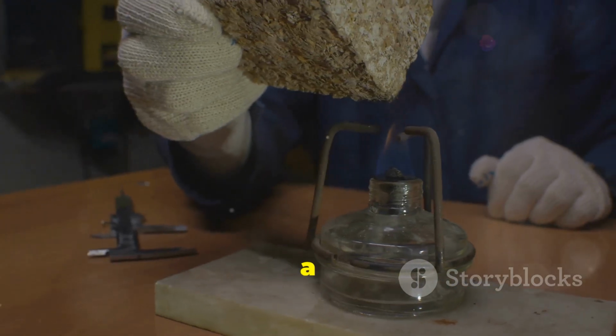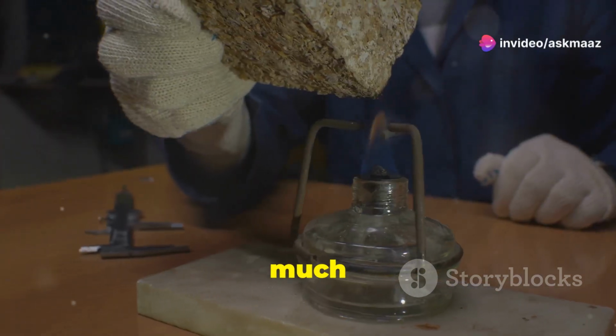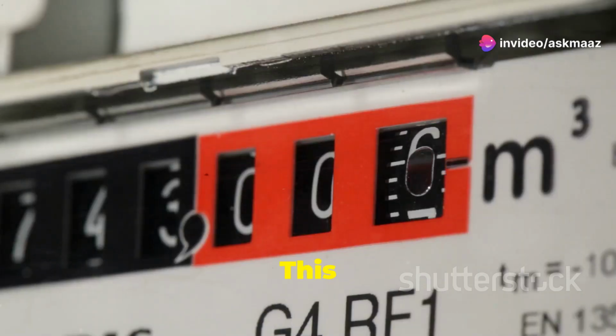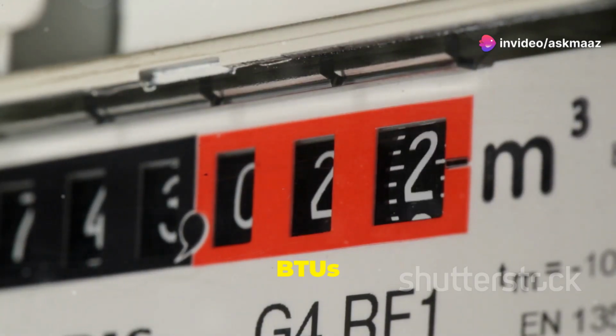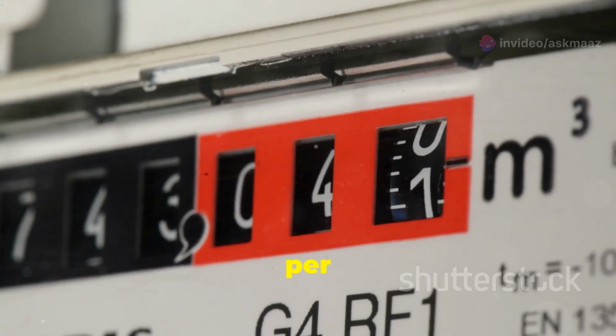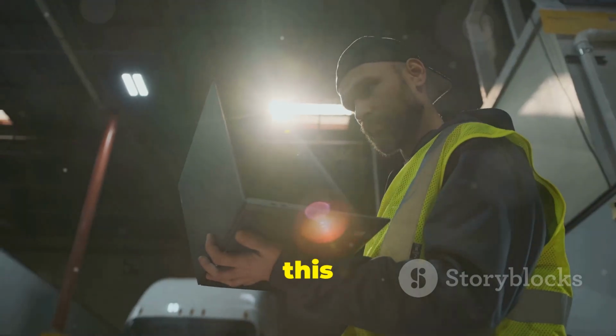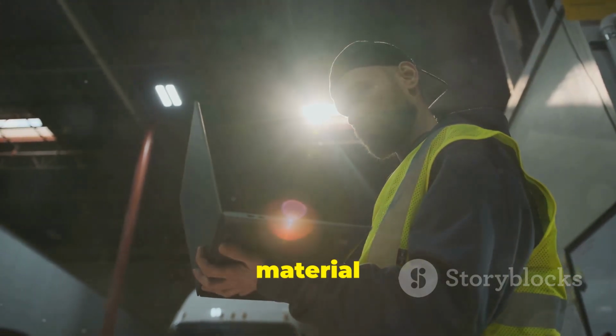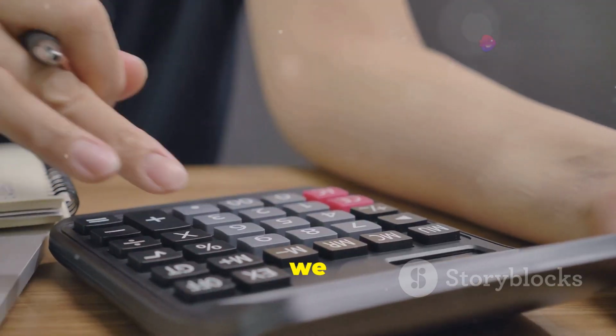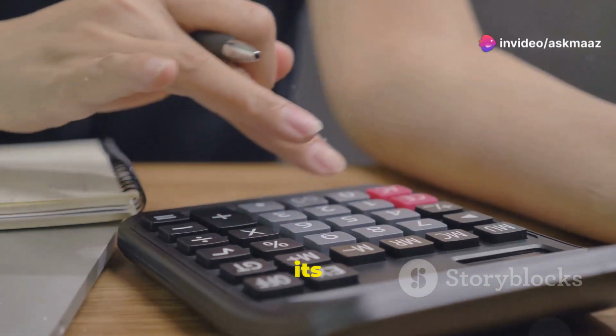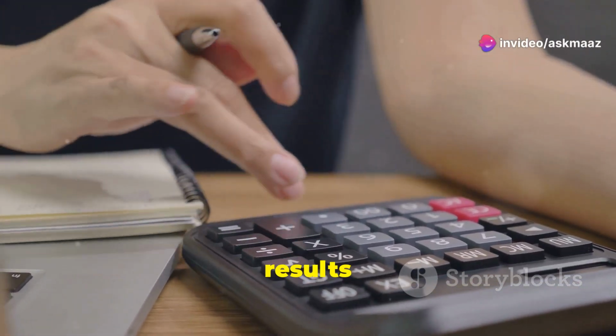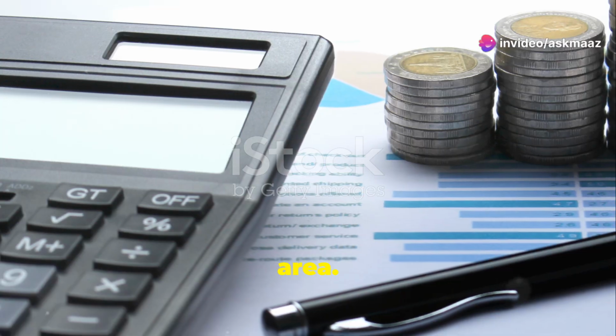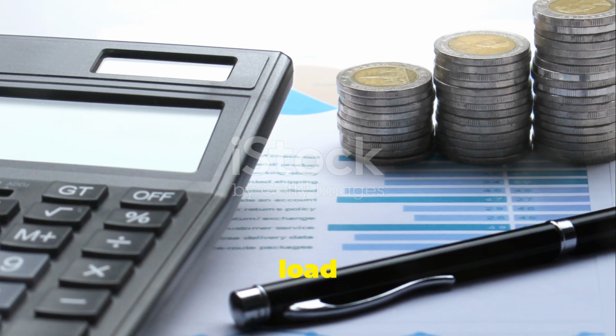Every material has a calorific value, which tells us how much heat it releases when it burns. This value is usually measured in BTUs per pound or megajoules per kilogram. You can often find this information online or in material safety data sheets. Finally, we multiply the weight of each material by its calorific value and add up the results for all the materials in the area. This gives us the total fire load for that space.